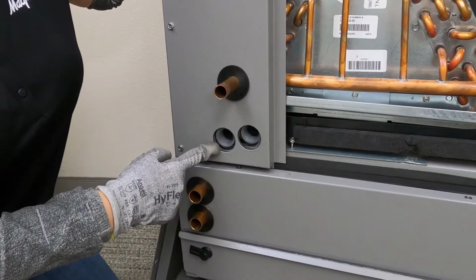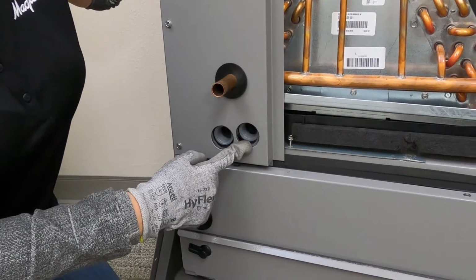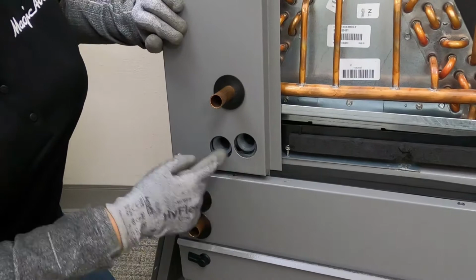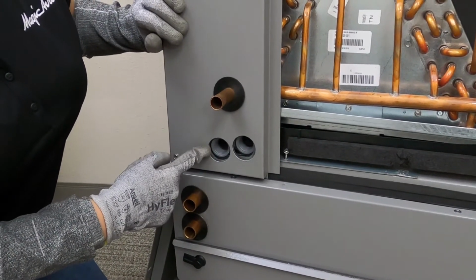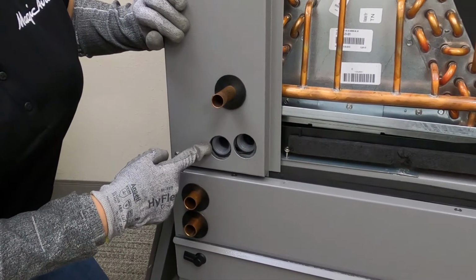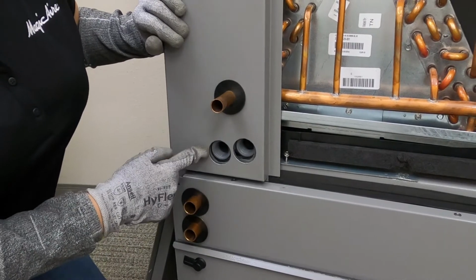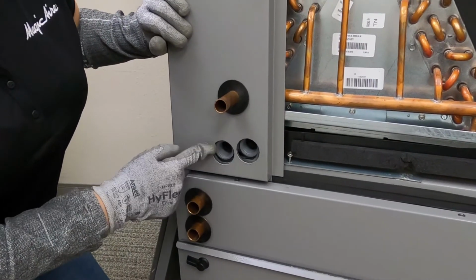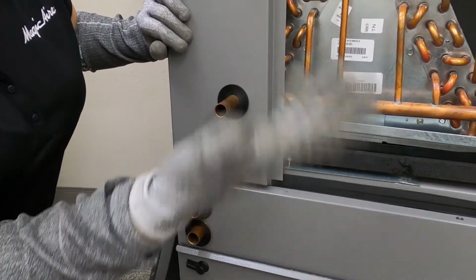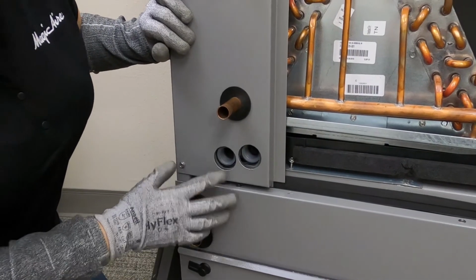This is the primary condensate drain and the secondary condensate drain. You will want to make sure that you keep these condensate drains cleared and cleaned out and that they're trapped properly. Backing up into the unit will produce liquid coming out and flooding the floor, and nobody likes that.